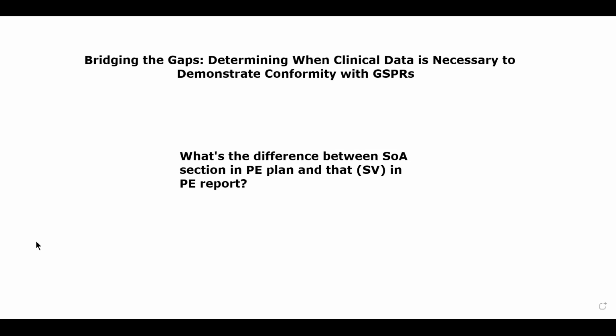You also want to describe things like the frequency and the epidemiology of that test being used in the general population, and any of the clinical guidance or diverging opinions of professionals, unmet needs of the testing technology, if there's any particular limitations or cross-reactivity or interference, as well as the clinical hazards or risks associated with incorrect test results in the general population. So they're going to be very similar. You will see quite a bit of overlap, but the SVR should go into more detail regarding the analyte and provide that scientific validity for the test as a whole.